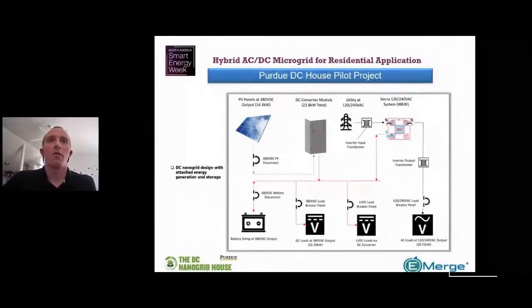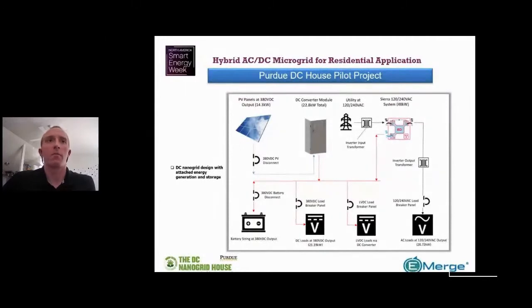Our nanogrid is composed of several pieces of equipment. We have a bidirectional inverter at the front with isolation transformers on the input and output. We have a DC-DC converter module connected to our solar panels — a 14.3 kilowatt installation on the house's roof. The DC-DC converter also has maximum power point tracking built in, and it helps regulate our 380 volt DC bus, which is the backbone of our nanogrid.